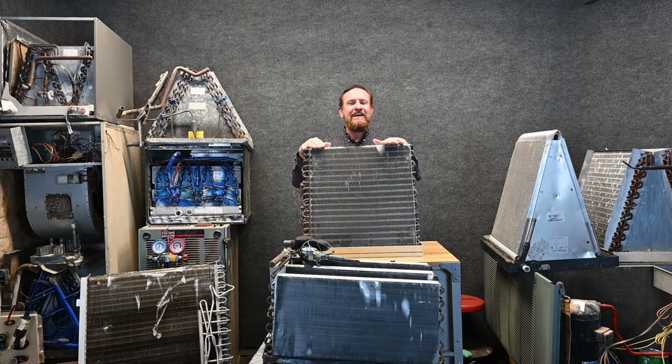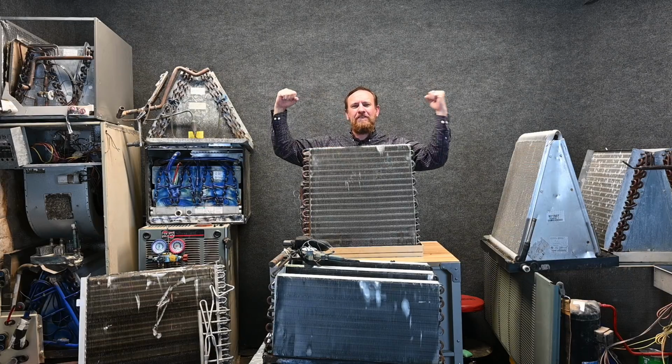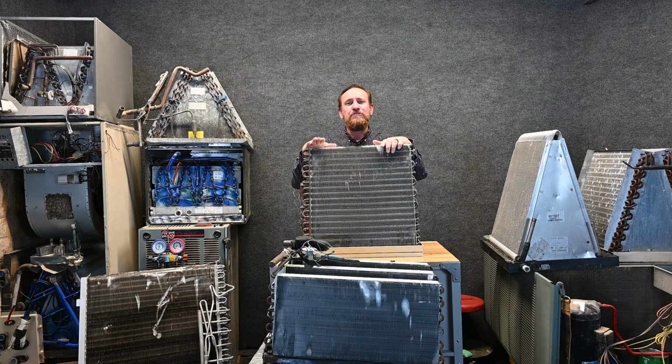So there's a difference in sizing and systems between different climates. The climate you're in, which is called a climate zone, which we'll talk about later, has different effects on how you size the system as well as how you're going to dehumidify. Notoriously, people want a larger AC. Bigger's better! Rah, rah, rah. On an AC system, it's not true. You want to have a matched house system. It's called Manual J, and there are several programs now used with that to help size the house as well as account for how much the house is leaking.